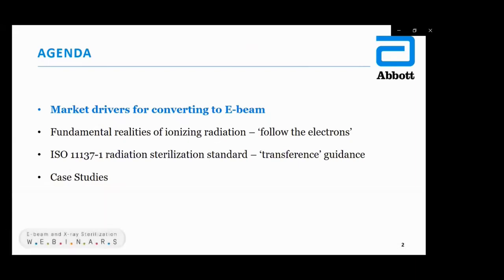We'll then discuss the physical realities of the three modalities of ionizing radiation used for medical device sterilization: gamma, e-beam, and x-ray. Despite gamma and x-ray being photons, it turns out that electrons are the main actors in all three modalities. Through that lens, we'll then discuss the guidance in the ISO 11137 radiation sterilization standards for transferring from one radiation sterilization modality to another.